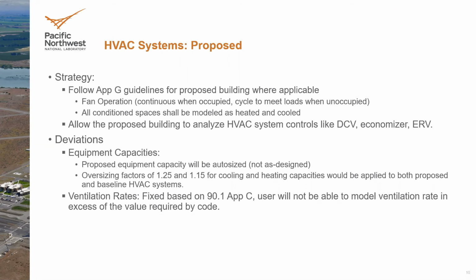I'm not - I mean, you're going to have your zone systems, and the DOAS system is going to provide temperature, so I don't know whether you'd call that reheat or not. But your zone systems are your single zone systems, and the DOAS is providing the fresh air.